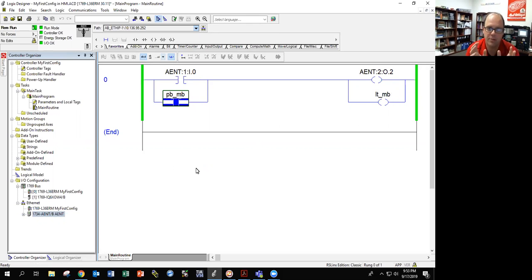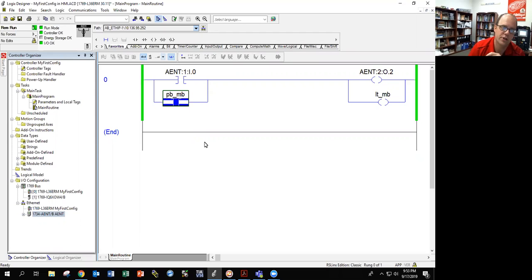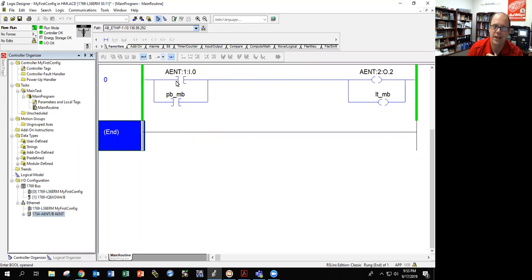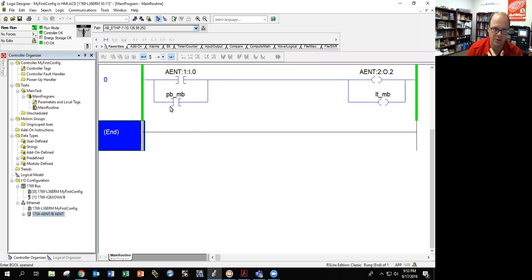When creating HMIs, create your program first. The program is important. Make sure that if you're going to have something controlled by an HMI, you create a memory bit. You can't link an HMI push button to an input on an input card — it's not designed that way. Do it with a memory bit. Always a bool. Doesn't matter what you call it, but make sure you know it's a bool, whether it's in your program or controller tags.